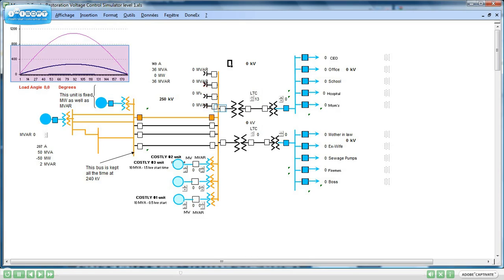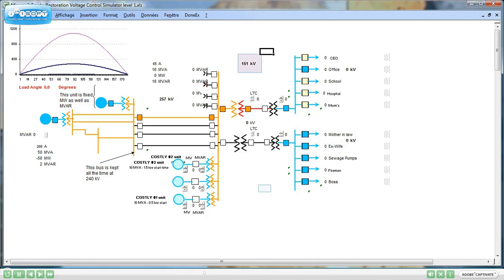Look at the load curve, and at the voltage on the 240 kV. Now let's energize transformers and pick up some load. Check the voltage on the 240 kV and on the 138 kV bus. Users will have to bring down the voltage using the load tap changer, because it is exceeding the maximum emergency limit, the voltage being just below the maximum emergency limit. Close the breaker and see the effect.